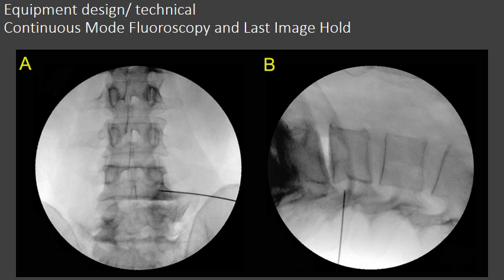So last image hold is used to retain the last image before the exposure goes off. And if you have this feature, there's usually two monitors, one that has the dynamic image on it, and the other one with the last image hold displayed. So this feature can reduce the beam on time by 50 to 80% because re-exposure to visualize placement is not necessary.